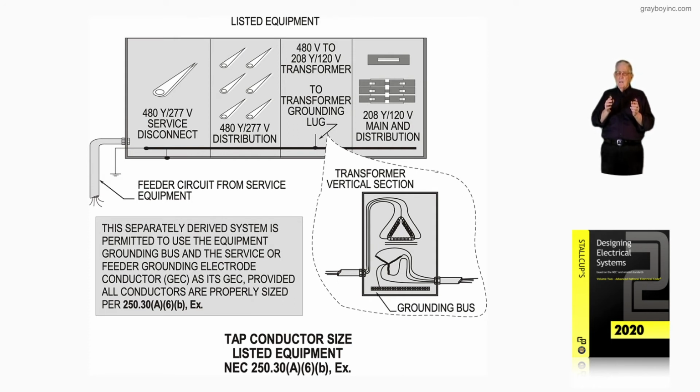So this really created a problem when you had an assembly, as you see, with that type of equipment in it. And you can bring in listed equipment with a lot of items in it, as you see there. So you have a 480/277 volt main with a panel or switchgear, switchboard that would have 480/277, feeding a transformer, stepping it down to 120/208, and even having a service panel there, as you see, panelboard with a main maybe.